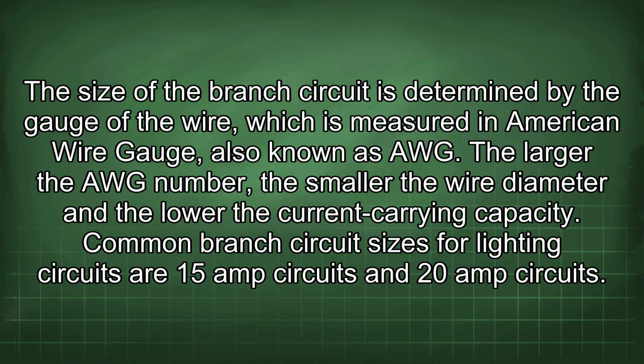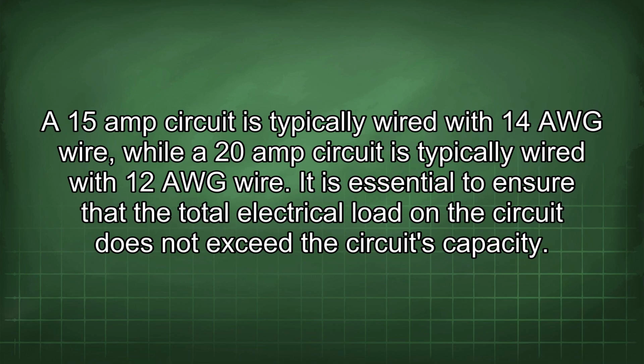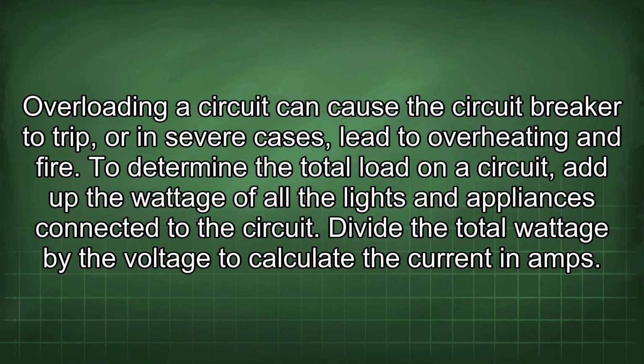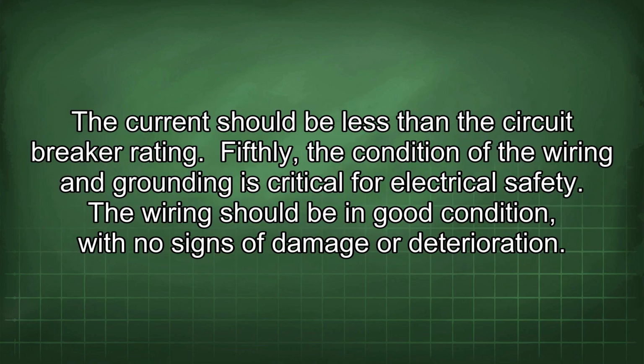Common branch circuit sizes for lighting circuits are 15 amp circuits and 20 amp circuits. A 15 amp circuit is typically wired with 14 AWG wire, while a 20 amp circuit is typically wired with 12 AWG wire. It is essential to ensure that the total electrical load in the circuit does not exceed the circuit's capacity. Overloading a circuit can cause the circuit breaker to trip or, in severe cases, lead to overheating and fire. To determine the total load on a circuit, add up the wattage of all the lights and appliances connected to the circuit. Divide the total wattage by the voltage to calculate the current in amps. The current should be less than the circuit breaker rating.